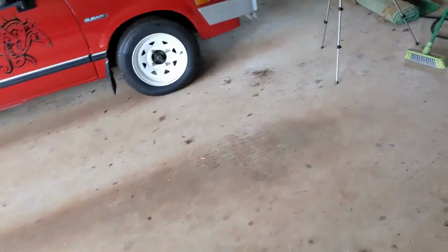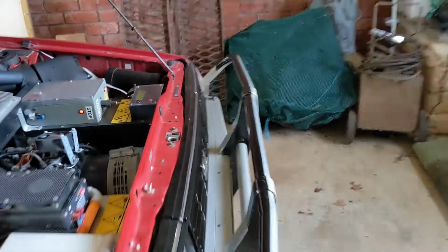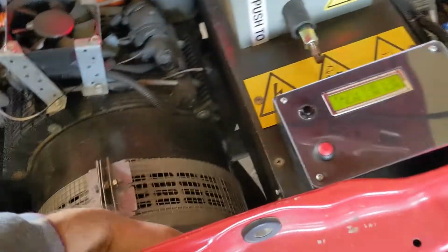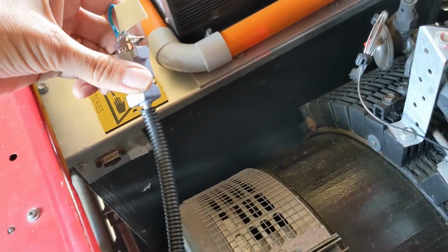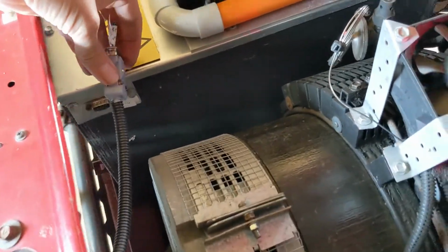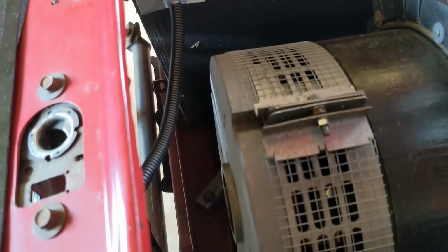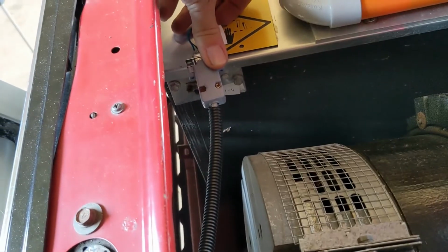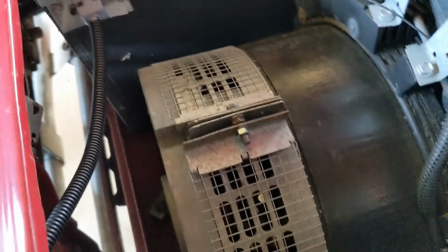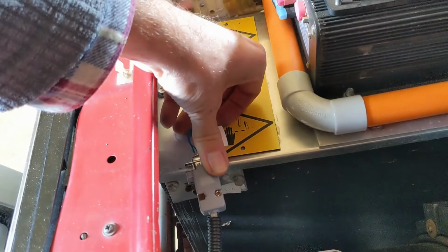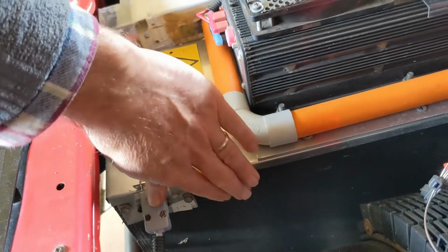So the next step to do is to put this, instead of, I had it tied back under there away from the motor, I'll tie it over here so that it's still running across the front of the motor. If that picks up interference, then it's presumably from the motor. If it doesn't, then presumably the interference is inside the box there.